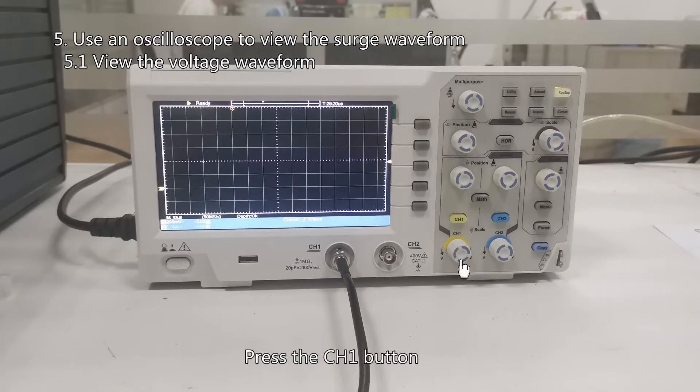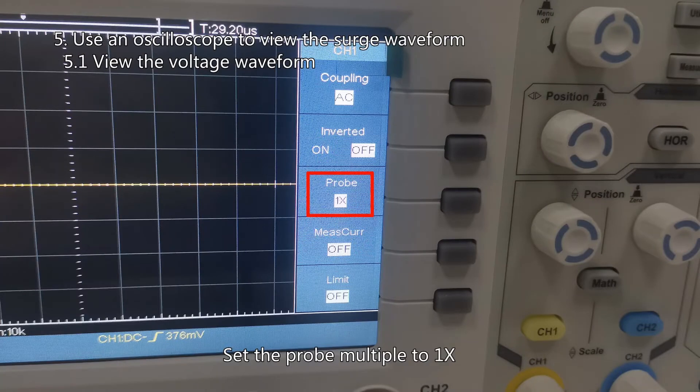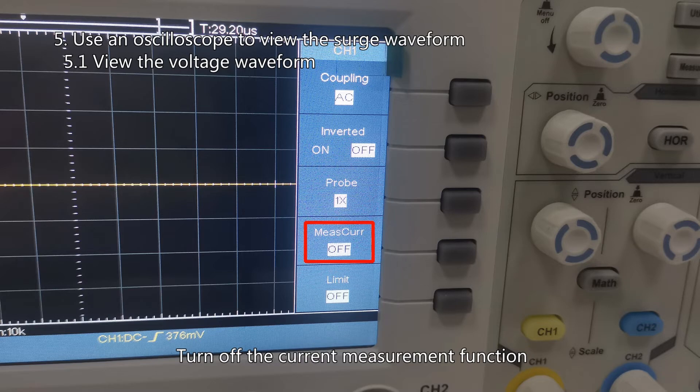Press the CH1 button. Set the probe multiple to 1x. Turn off the current measurement function.